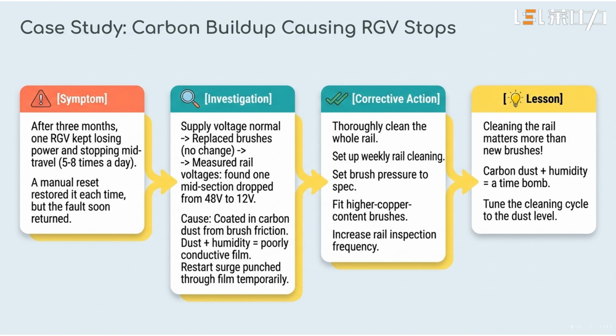Here's a very representative case. An RGV broke down 5 or 6 times a day. A manual reset fixed it each time, only for it to recur. Replacing the brushes didn't help. Finally, they found a thick layer of carbon dust on a mid-section of the conductor rail. Sooty dust from long-term brush friction had built up. With the humidity, it formed a poorly conductive carbon film. Wherever the RGV reached that section, the power failed.